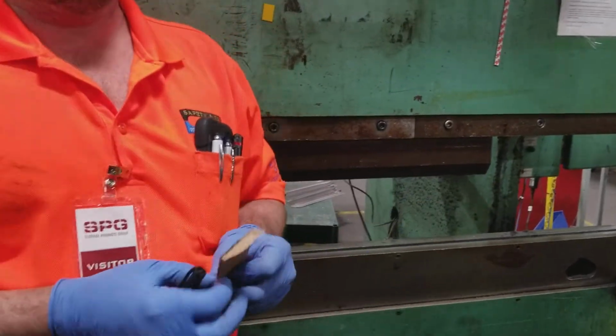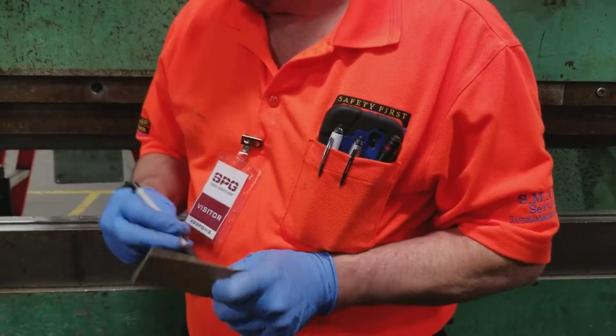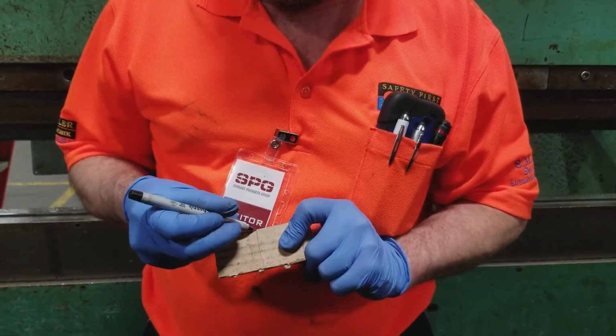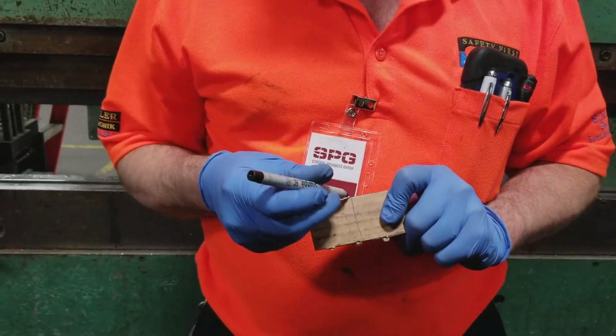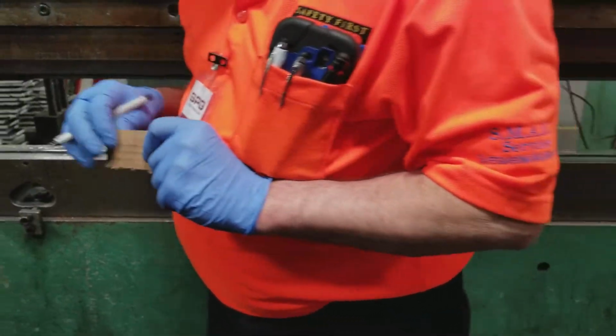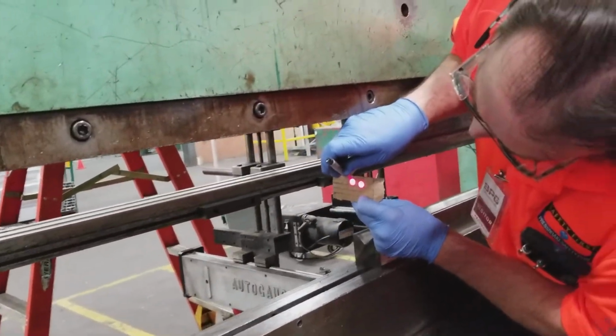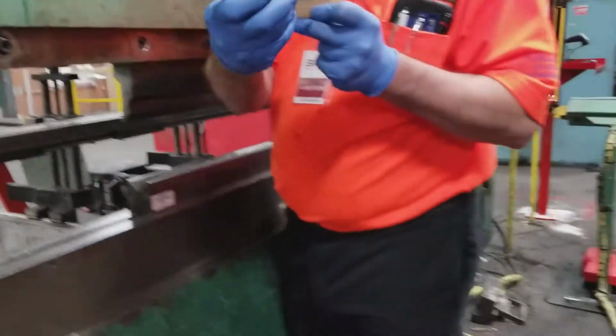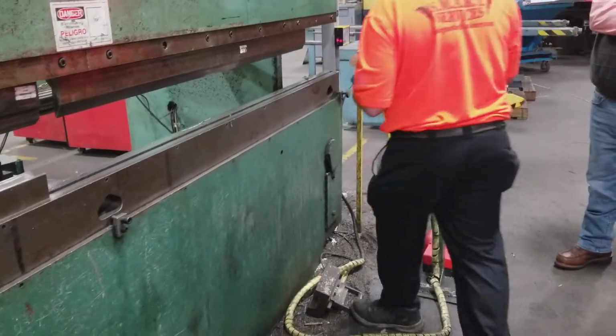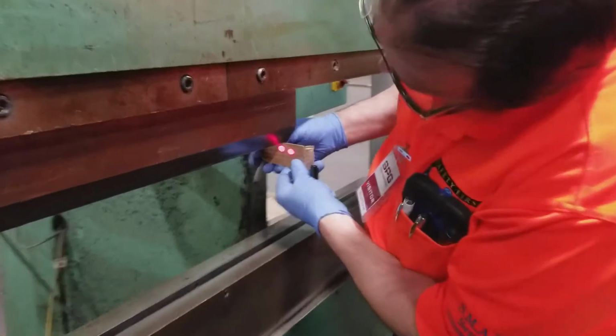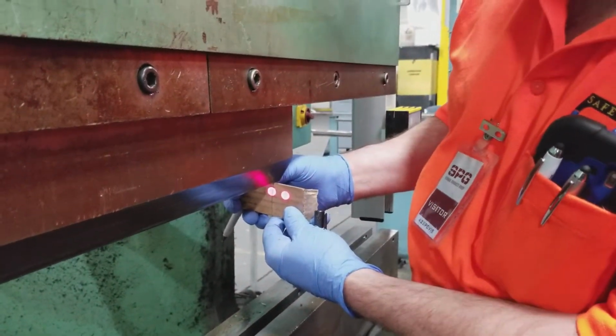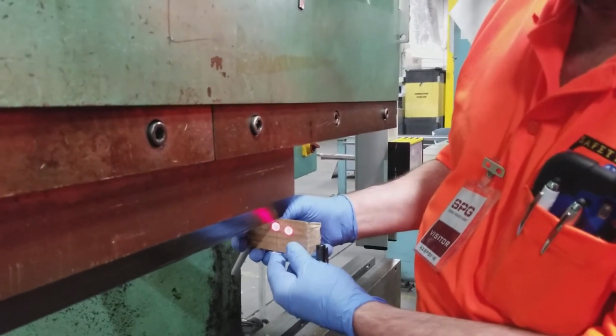What we're going to do is check the alignment of the transmitter. We'll take this line and place it at the tip of the upper tooling, so the peak of the upper tooling is right there at the line, on the left side of the tool. We'll hold it like so, then take a marker and mark the top edge of the laser. This gives us a crosshairs effect showing where the laser should be located. Now we'll take it to the right side, hold it up in the same location, and it should be pretty much identical—which it's pretty close. That's how you check the alignment of the transmitter.